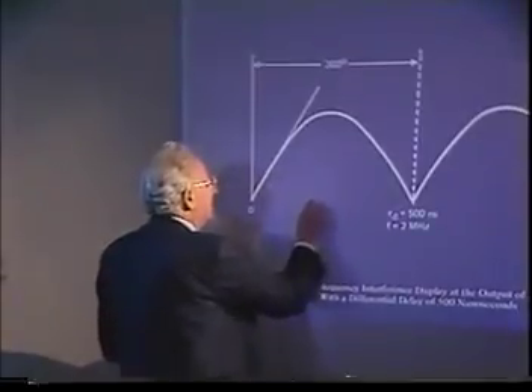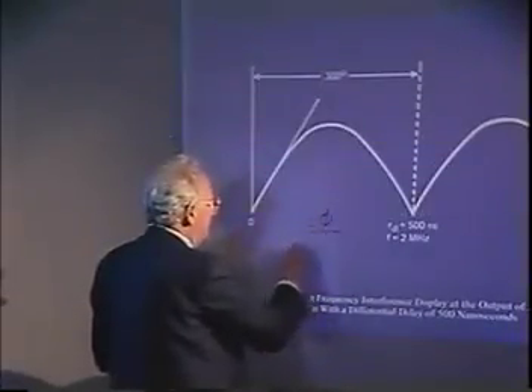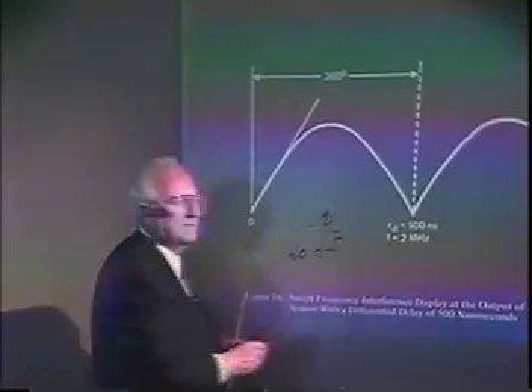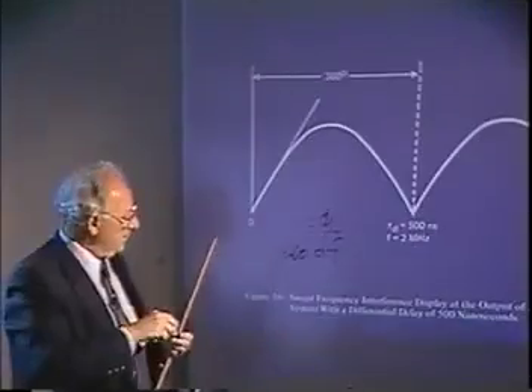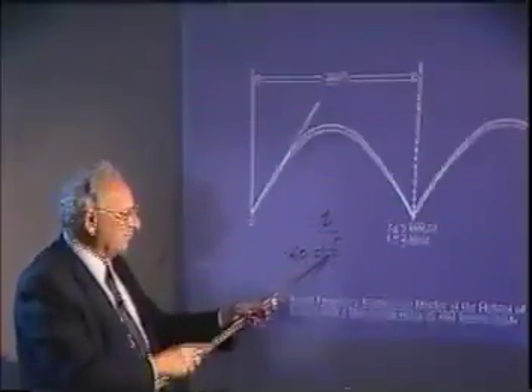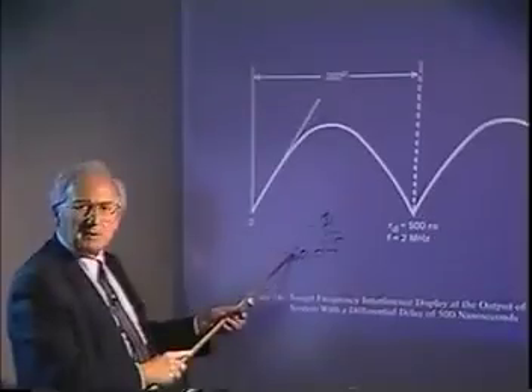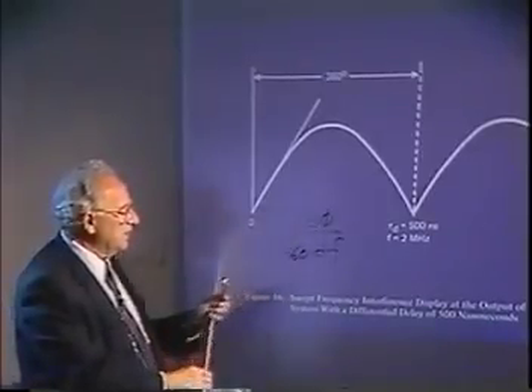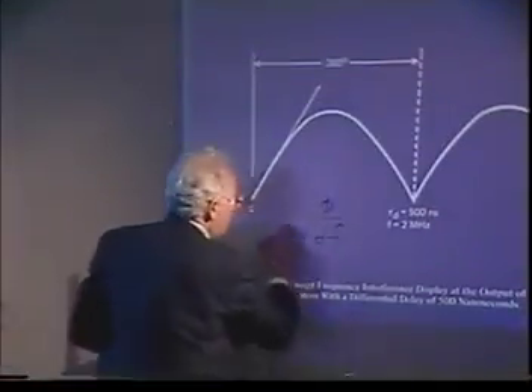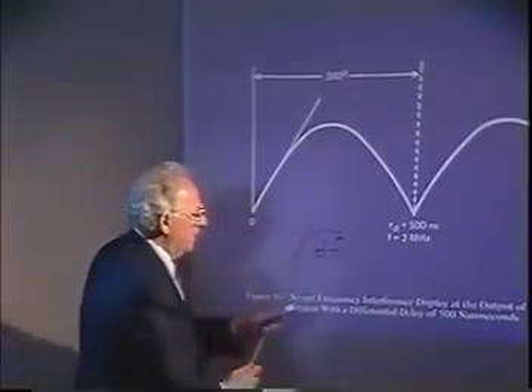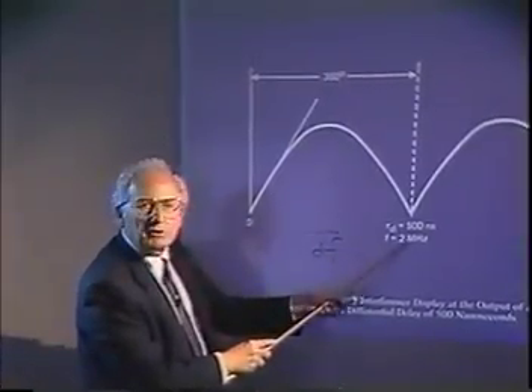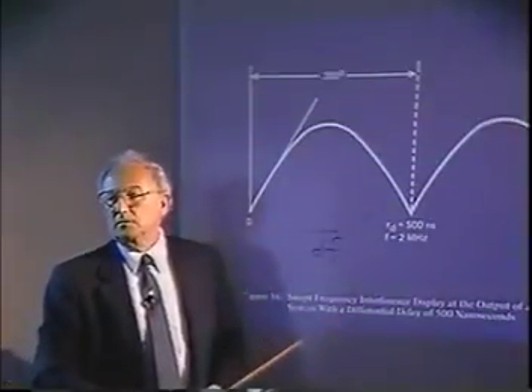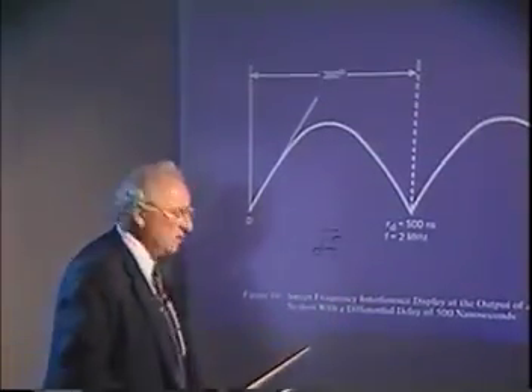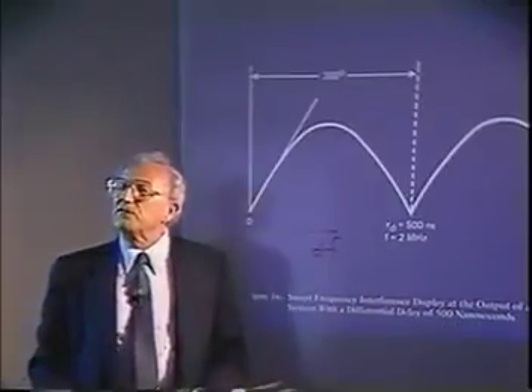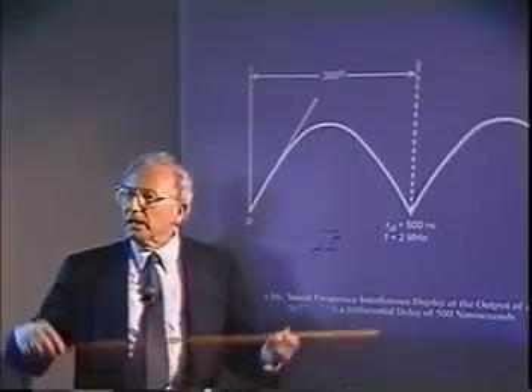In other words, the equation is this. That's the equation. Delta phase over delta frequency, where delta frequency is multiplied by 360. Now if you vary this phase so that it's 360 degrees, this disappears, this becomes 1. You have 1 over the change in frequency. 1 over the change in frequency of 2 megahertz is 500 nanoseconds. That's the length of the line. So the differential length of the delay line is where you'll see the first null. The differential length between the two channels.